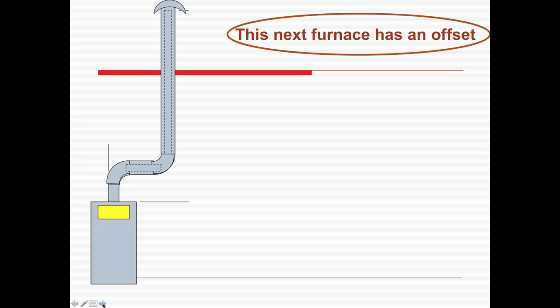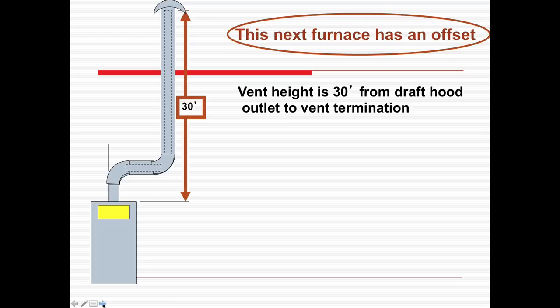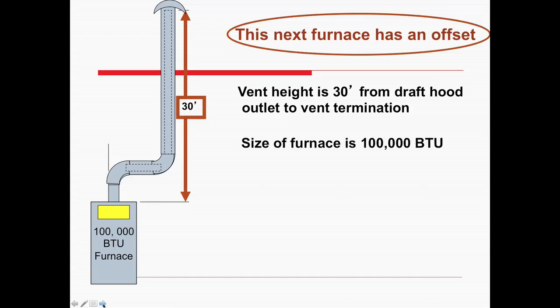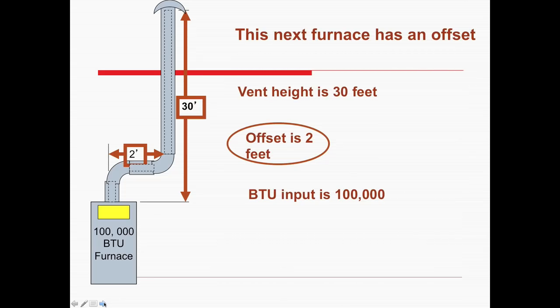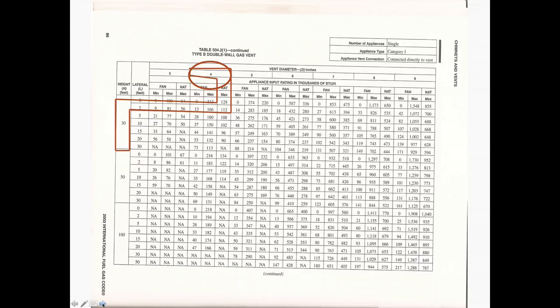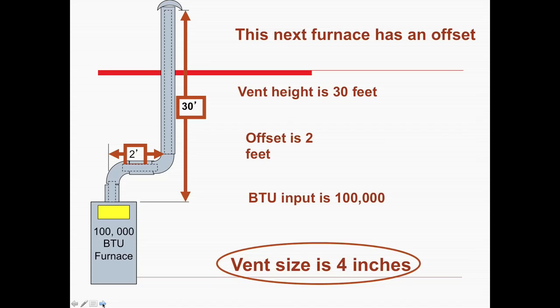This furnace has an offset. We're still using B vent. The height is 30 feet, size of the furnace 100,000 BTUs — same as the other one — with a two-foot lateral. Going to 30 feet, with the two-foot offset we use the two-foot lateral. With that two-foot lateral we can do 112,000 BTUs. So the vent size is four inches.